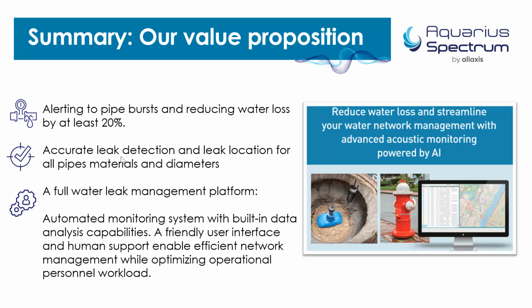We provide accurate leak detection. In terms of accuracy, it is plus minus 3 meters on either side of the leak. This is achieved also using this very large distance between sensors or hydrophones in multiple projects that can be distanced by 800 meters. Will keep this accuracy.